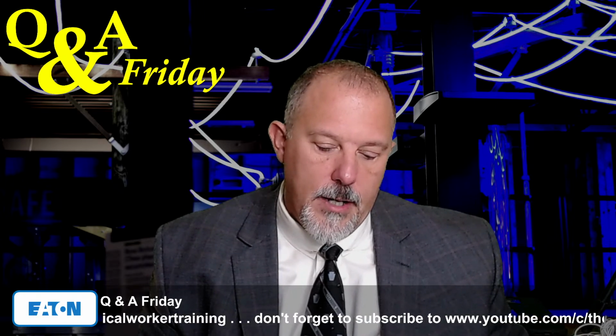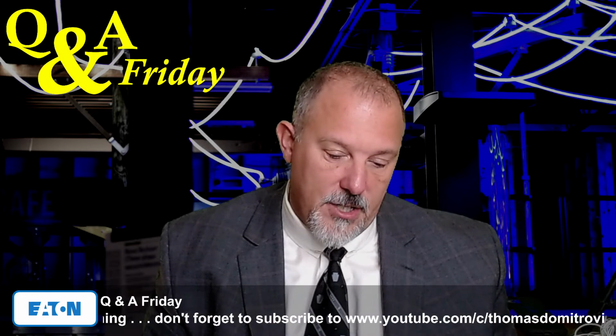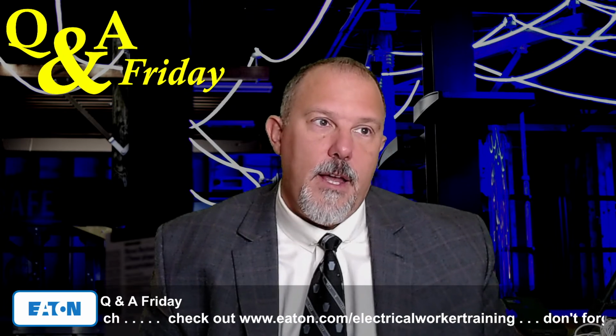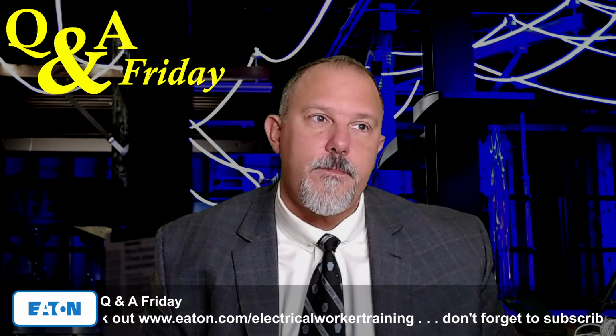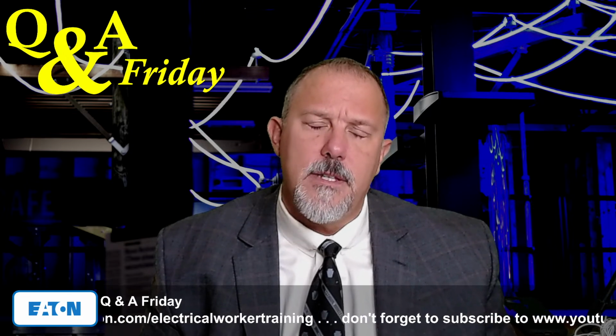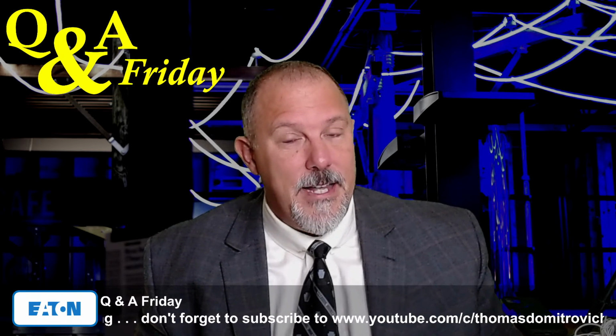And I'm trying to remember the specific section. Oh, man, it's right on the tip of my nose. But in any case, that is correct that when you have a service overcurrent protective device, the moment you land conductors on the secondary, it also is a feeder overcurrent protective device. And I think in the discussions that we were having, we were talking about a branch circuit and a feeder, and that there weren't similar rules in 230 for service overcurrent devices.